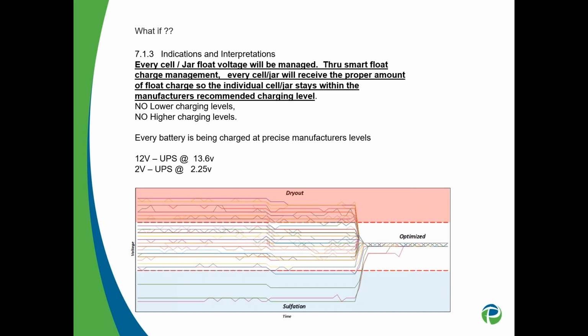You'll see a longer service life, a higher capacity. You'll actually get a better impedance or ohmic value measurement, because that value is heavily influenced by your float voltage. And a huge cost savings, because you're able to extend that service life from 5 to 6 years to 7 and 8. That's a huge cost savings when it comes down to it.